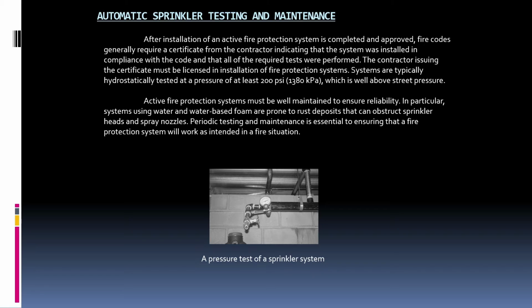Active fire protection systems must be well maintained to ensure reliability. In particular, systems using water and water-based foam are prone to rust deposits that can obstruct sprinkler heads and spray nozzles. Periodic testing and maintenance is essential to ensuring that the fire protection system will work as intended in a fire situation. And this is the image of a pressure test of a sprinkler system.